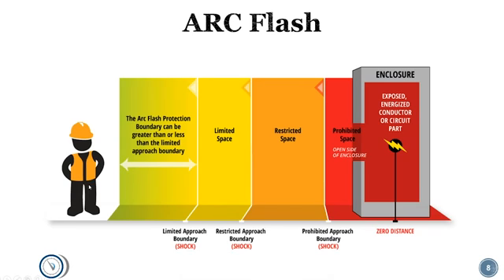When you think about the arc flash boundary, you want to be really careful about getting no closer to the equipment than you need to, unless you're wearing your full appropriate PPE. I'm not going to go fully into what PPE you need, but be aware that when working in industrial and commercial environments, including pulling panels off higher voltage air conditioning systems, you need to make sure that as you approach, you're properly covered with your personal protective equipment, which is what PPE stands for.